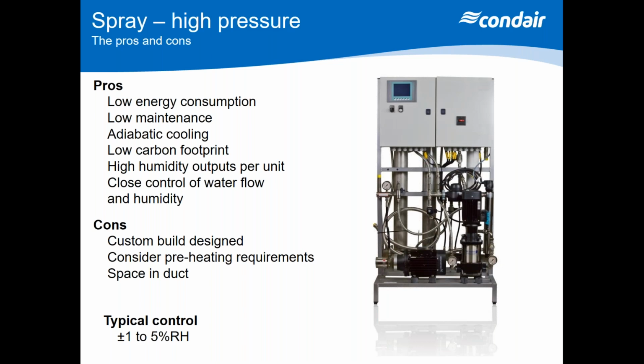Now, with a high-pressure spray system, it's going to differ from the water system in that the droplet sizes are going to be slightly bigger. So you might need more distance to spray with a high-pressure system, but you're also going to find there's less noise. So you can use these in areas where maybe they're more occupied and there's not too much of an issue with noise. So that will help obviously with the application. These can give you control down to plus or minus 1% in certain applications, because they can give you stages of control either in lines of valves, lines of nozzles, or numbers of spray systems in room.